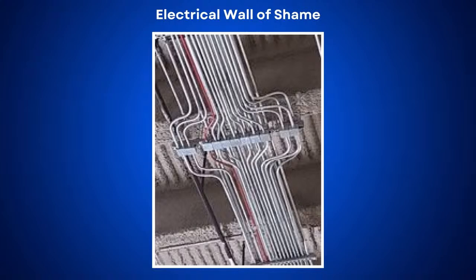Yeah, and then like we kind of said too, with the conduit entries, inspectors start seeing this kind of stuff, they're gonna be like, hey, let's start checking box fill, because how many conductors did you have to bring through there? And I think I saw earlier, if you look at this picture close up, there's a flex that comes out of the top of one of them and connects to another one, and you're like, wait, how did you do that? Let's just say hypothetically they put a wireway in there. Now you've got to start looking at how many conductors, because once you get over 30 current carrying conductors, you have to start derating. Yeah, that's a valid point too.